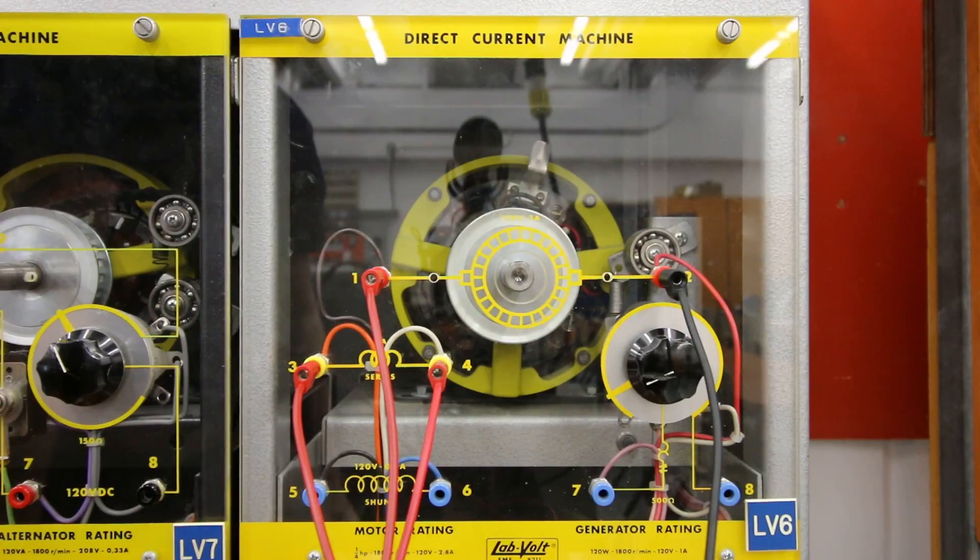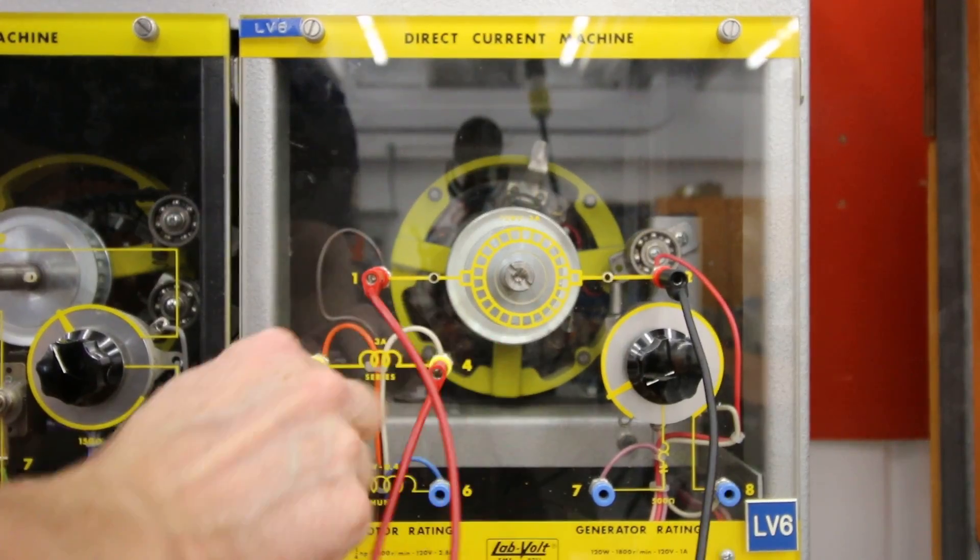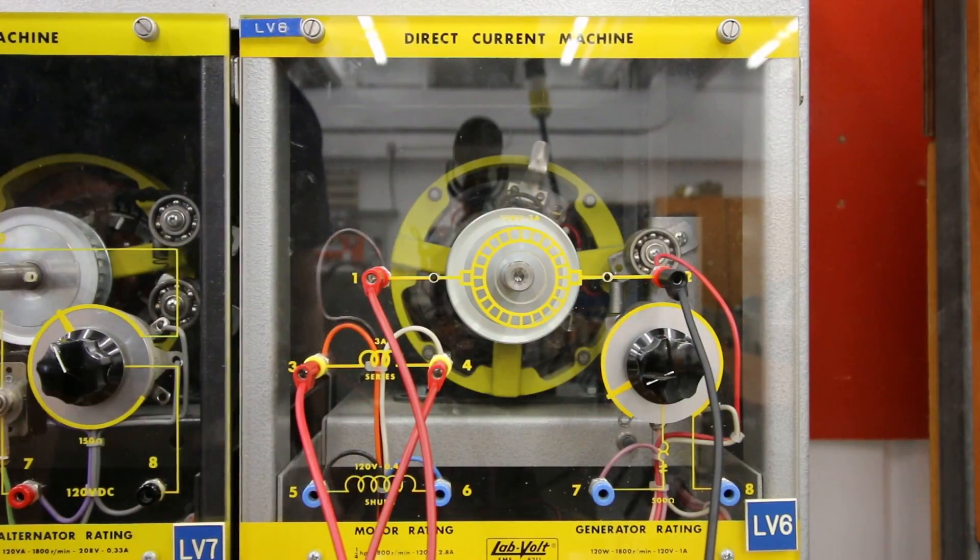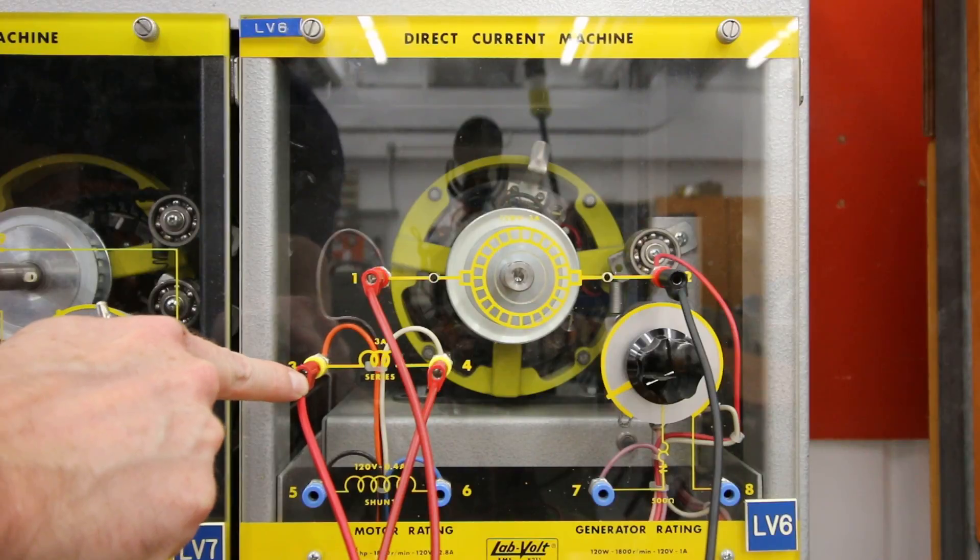In order to change the direction of rotation of the series motor, you can change either the armature or you can change the series. Okay, we're going to keep it like this. Bump it. And you can see that by putting our supply into here, it's going in a clockwise direction.